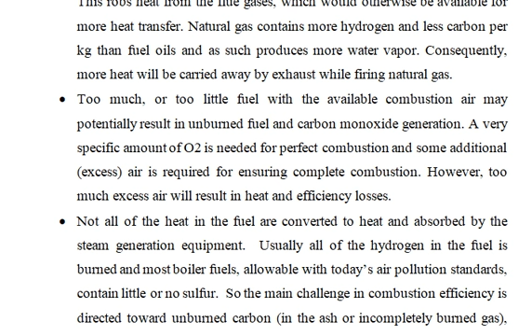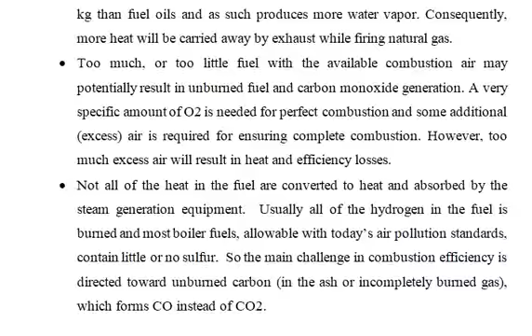A very specific amount of O2 is needed for perfect combustion. Some additional air is required for ensuring complete combustion. However, too much excess air will result in heat and efficiency losses. If you are supplying more air, what happens? Complete combustion takes place, no problem. But whenever excess air is supplied, there is no use of that oxygen. That means you have heat losses and reduced efficiency.